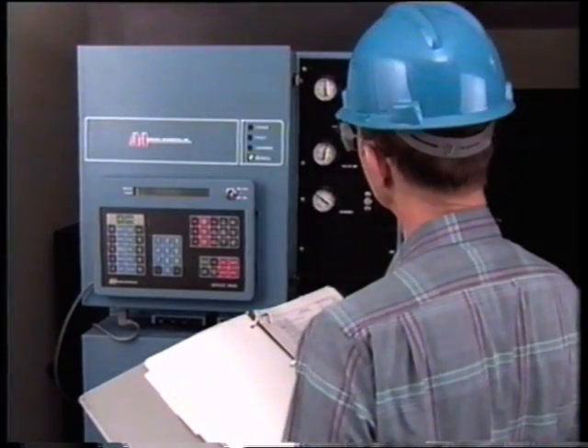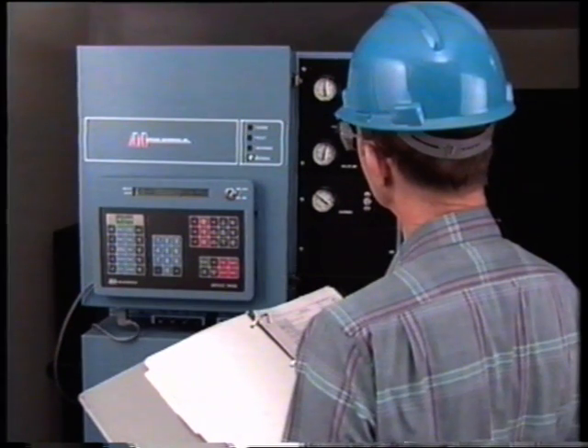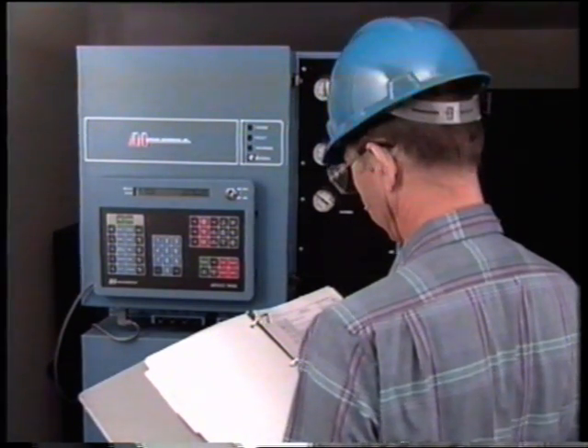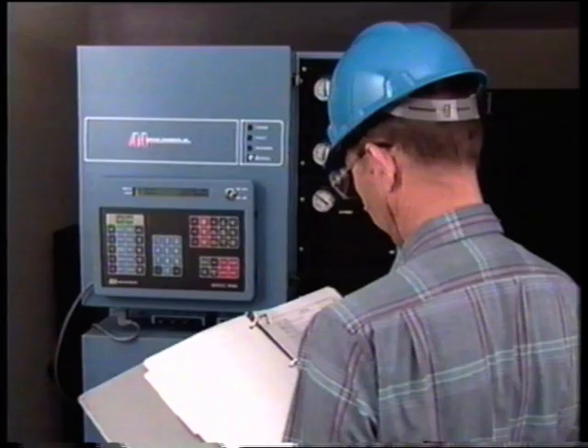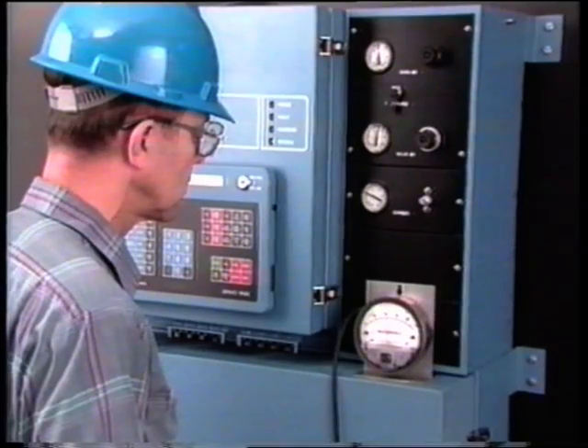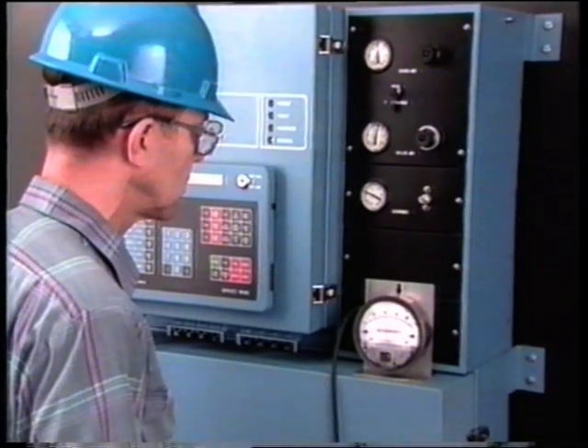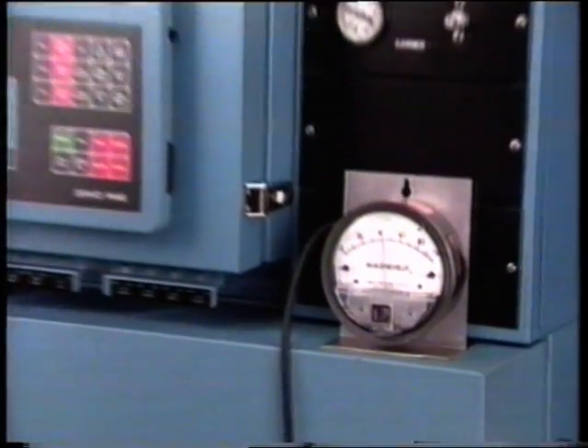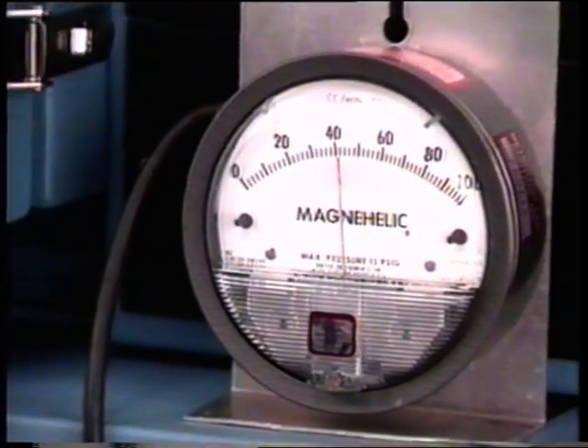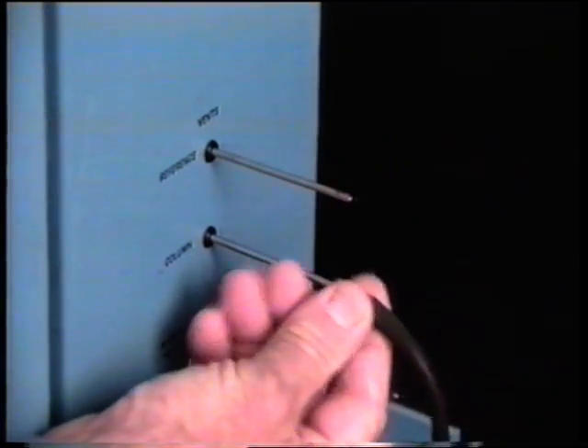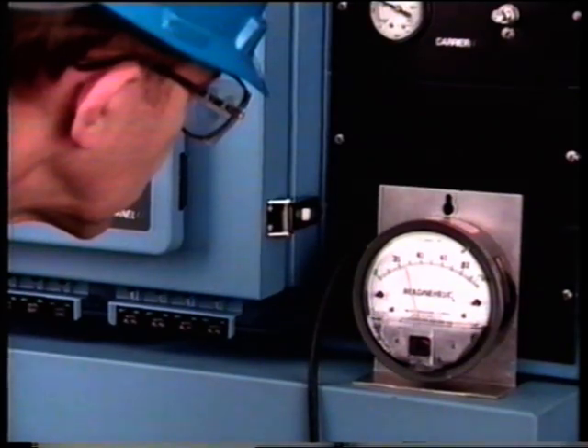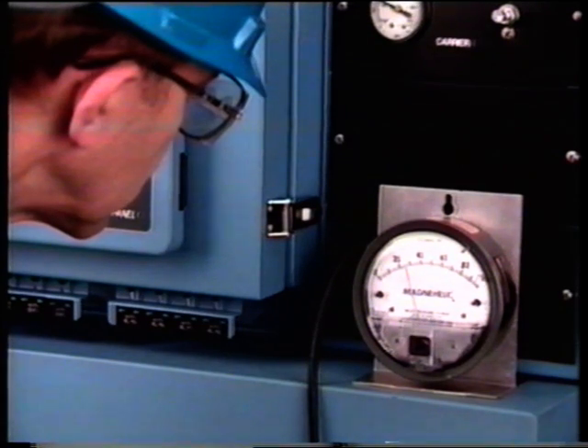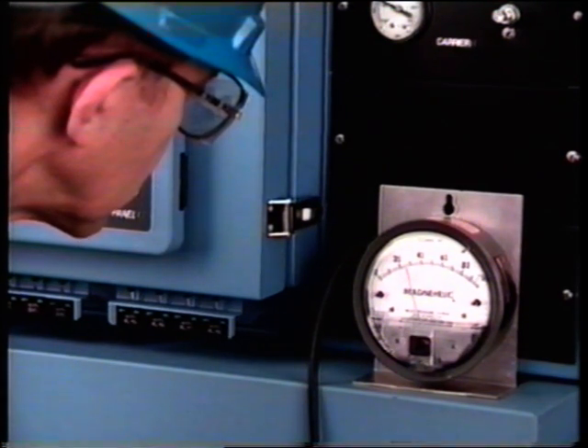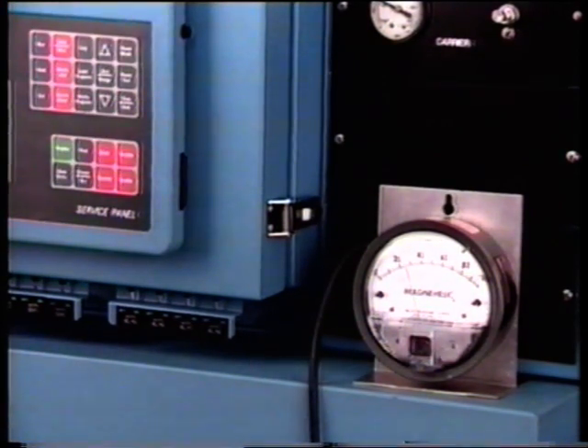With the analyzer in operation, check that carrier flow from the detector reference vent and the column vent meet manufacturer's specifications. To do this, attach a calibrated magnehelic or other flow meter to the reference vent line. In this case, the reading is correct. Repeat this process with the column vent. If there is no flow, or if the flow has changed from one or both vents, a detector tube may be blocked or restricted, and it should be changed.